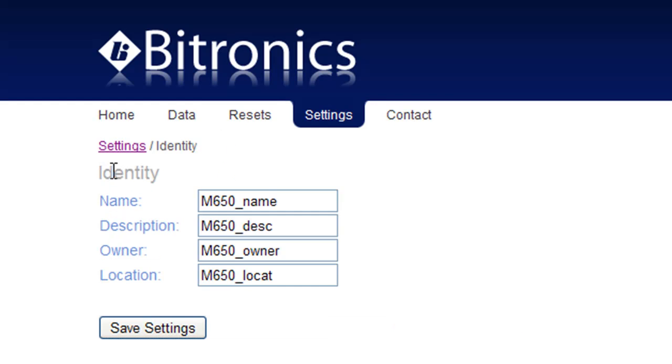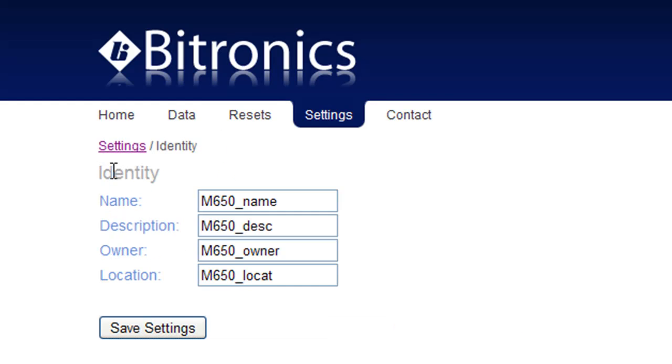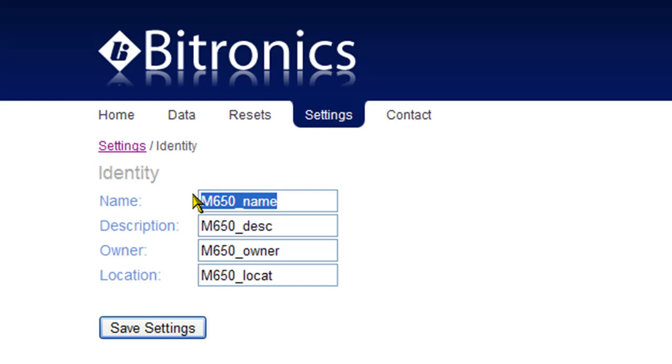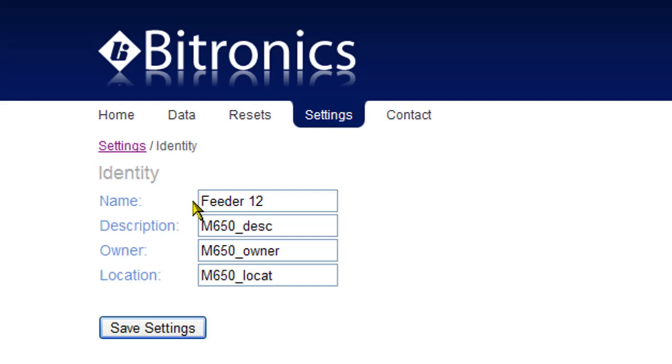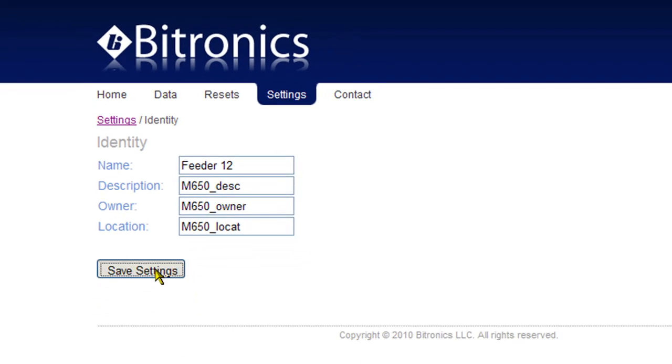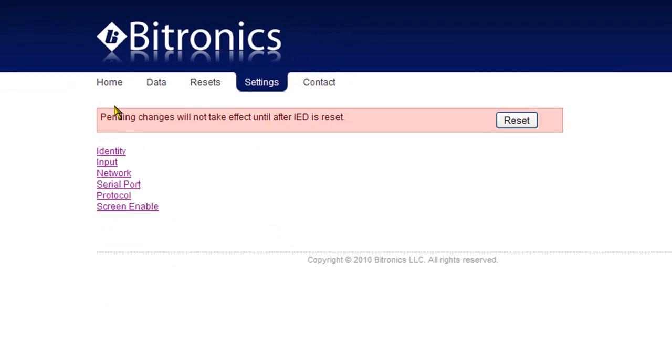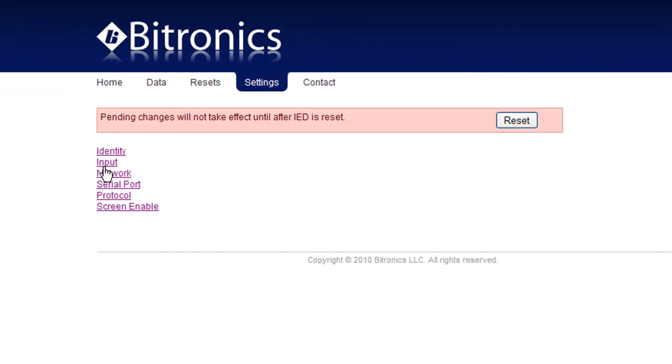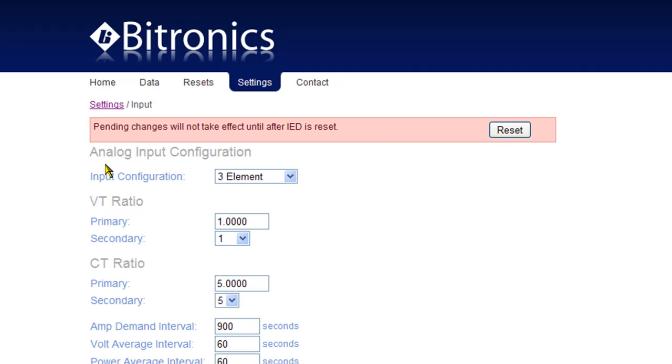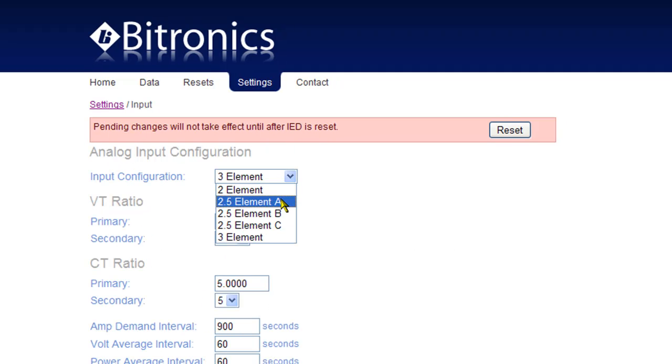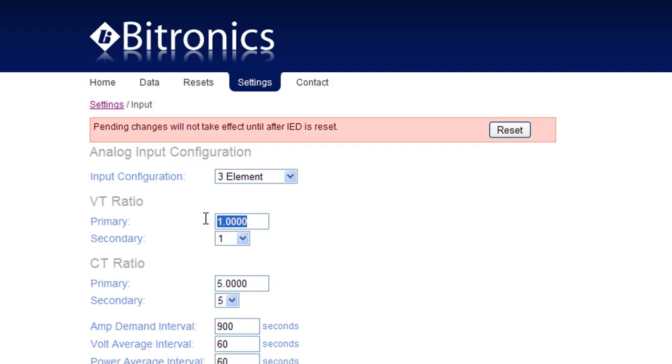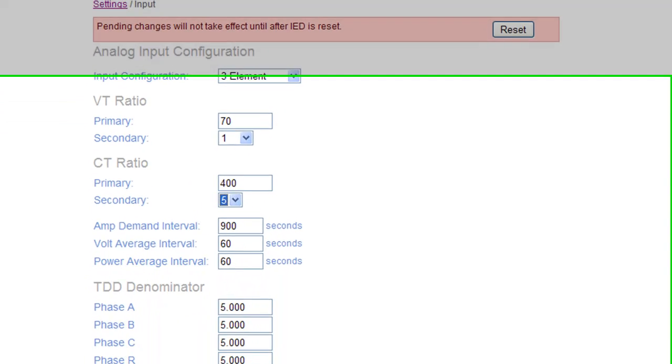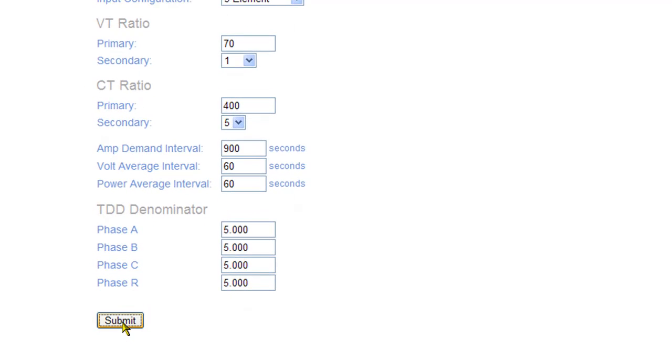Identity is where you might indicate the name of the line being monitored by the meter. Inputs is where the meter is configured to operate on a delta or a y-connected system and where the scaling is entered to account for the CT and PT ratios. Click on the submit button after making any changes to save them before navigating to any other page.